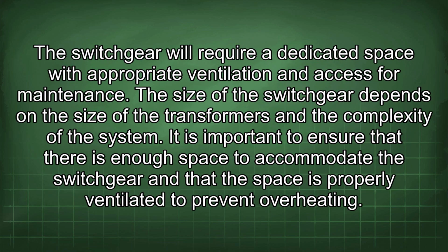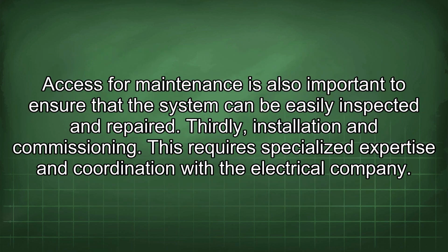The switchgear will require a dedicated space with appropriate ventilation and access for maintenance. The size of the switchgear depends on the size of the transformers and the complexity of the system. It is important to ensure that there is enough space to accommodate the switchgear and that the space is properly ventilated to prevent overheating. Access for maintenance is also important to ensure that the system can be easily inspected and repaired. Thirdly, installation and commissioning.